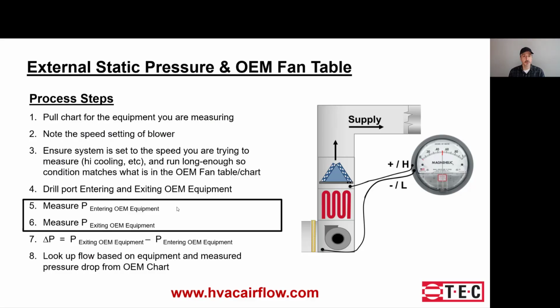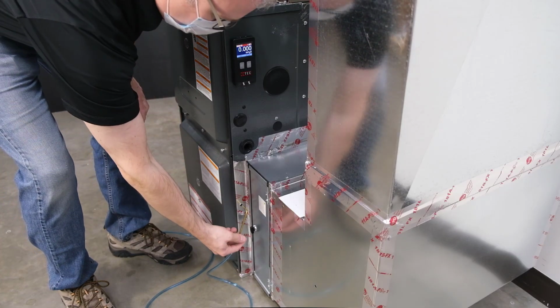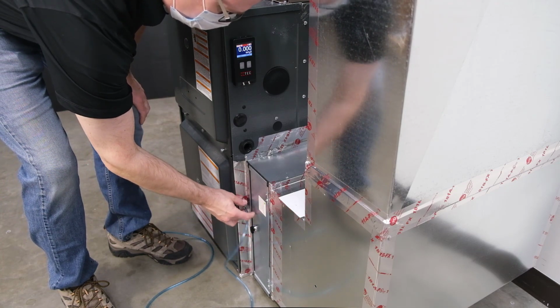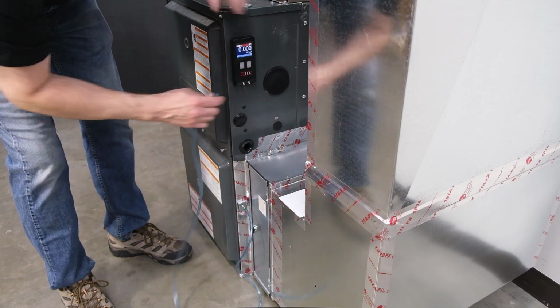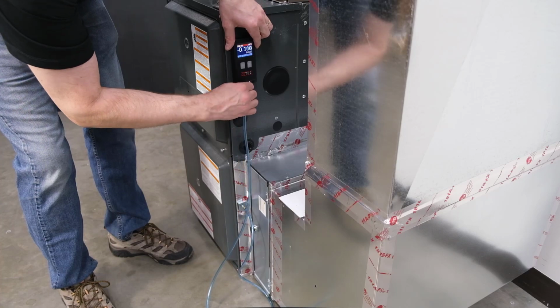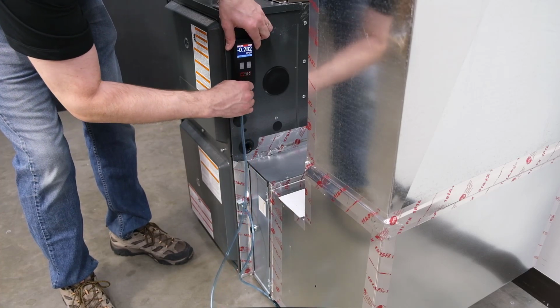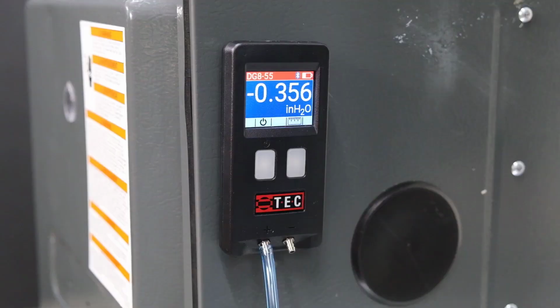Okay, with the ports in place, now we're ready to make the measurements. So let's take a look at Steve doing that. Here he is inserting the static pressure probe on the entrance, and then he's hooking it up to the DG8. You could already have the tubing connected to your manometer as well. A reading of about negative 0.36.